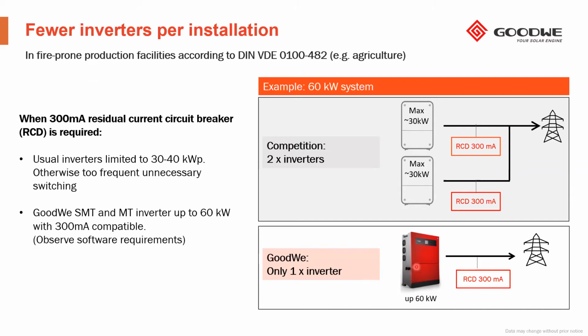This software keeps control of the inverter to avoid higher residual current. That means we can install one RCD up to 60 kilowatt, when in the market usually you find you have to be limited by this restriction with inverters up to 30 kilowatt. So it's quite relevant, especially for this kind of application. That, in my opinion, also belongs to the C&I, as a subsegment of the commercial and industrial portfolio.